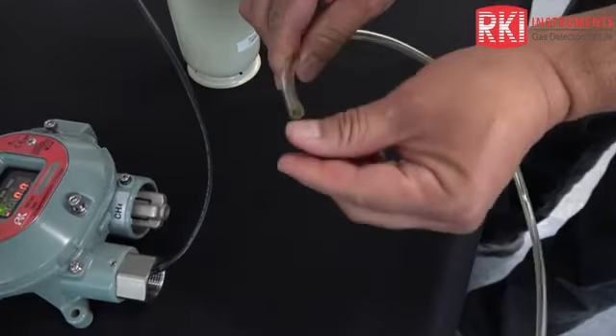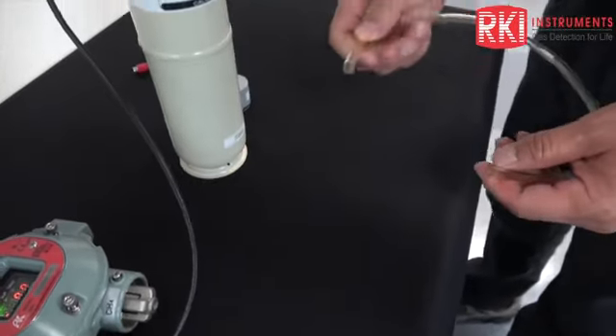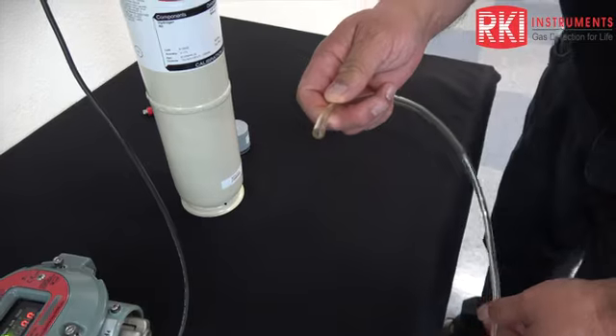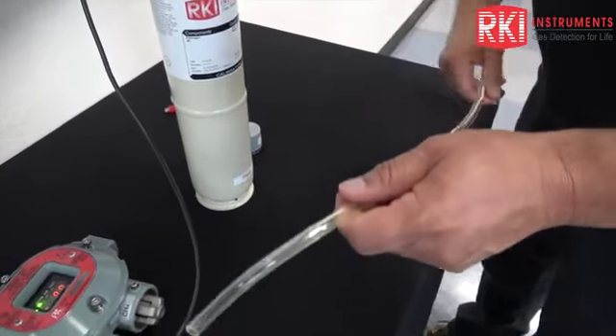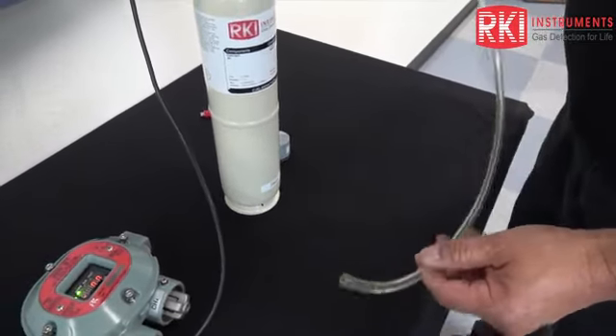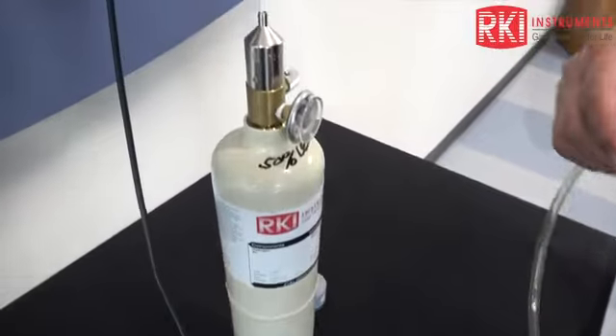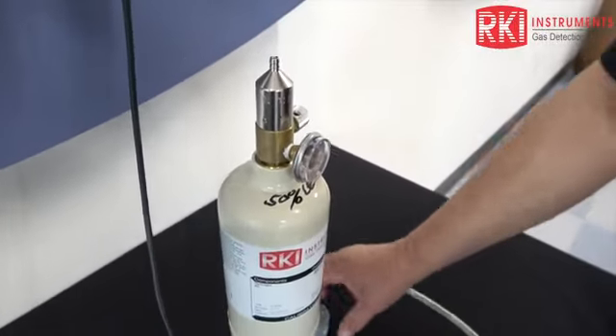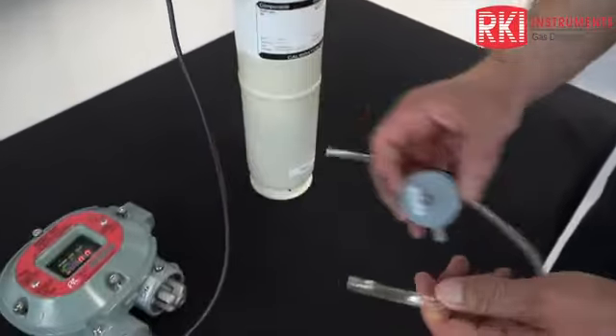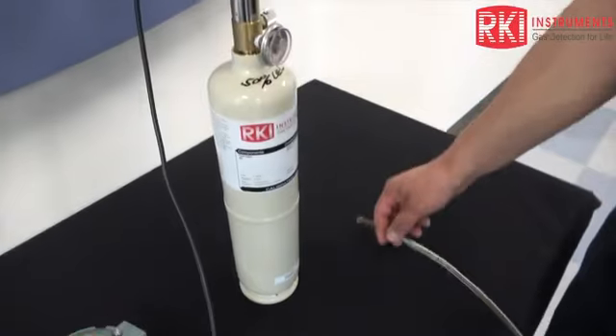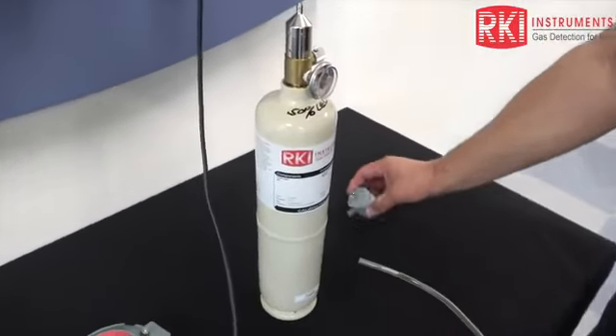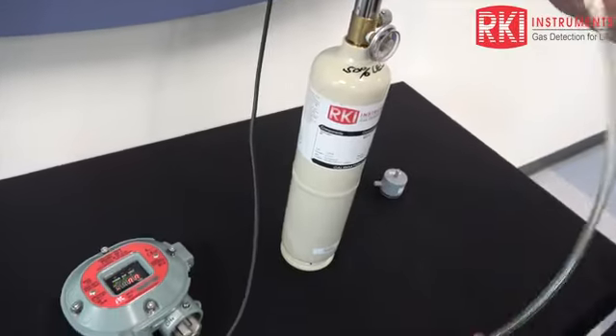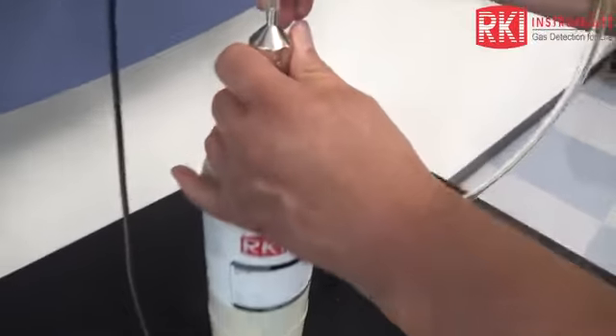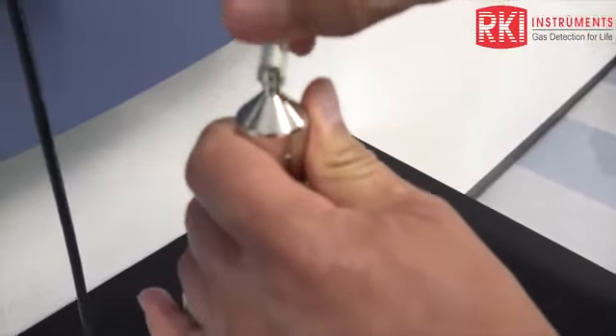And then there will be little fittings on each end where you can fit one fitting into the calibration tubing, and the other fitting could go onto the regulator. Or rather, the cal cup, I should say. The one end into the cal cup, one end to the regulator. So you'll have little tube sections that'll allow you to do that. So basically, I'm going to connect my calibration tubing right now onto this hose barb regulator.